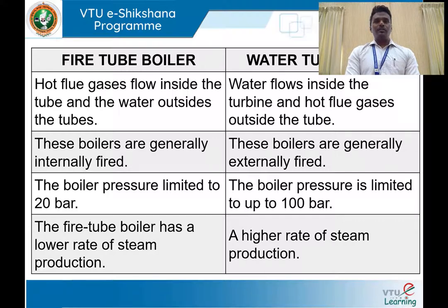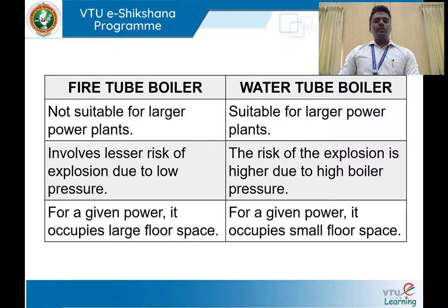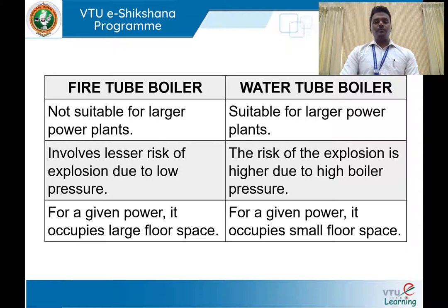In a fire tube boiler, since the tubes are housed inside the boiler shell, the shell thickness is less, which limits steam generation at very high pressure. Fire tube boilers also have lesser steam generation capacity. The water tube boiler, because of its excellent heat surface area, provides a higher rate of steam production. Fire tube boilers are used in industries like paper, sugar mills, and refineries, but cannot be used for electricity generation in a steam power plant. Water tube boilers can be used for larger power plants.